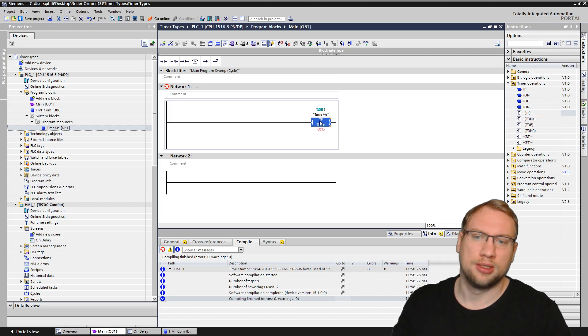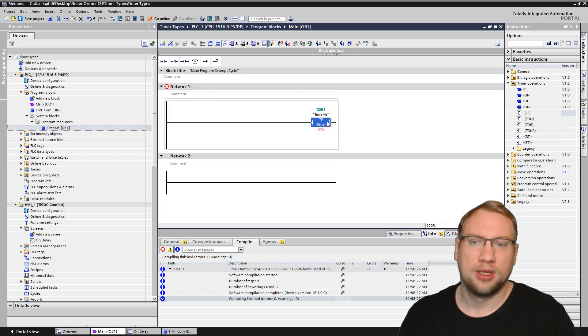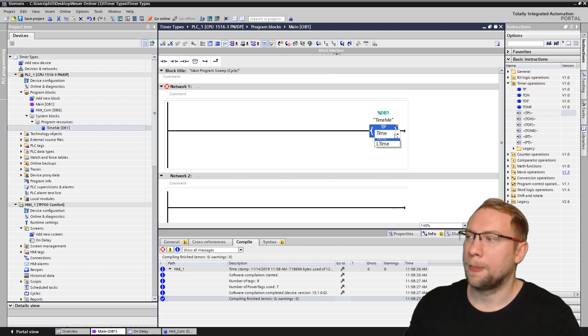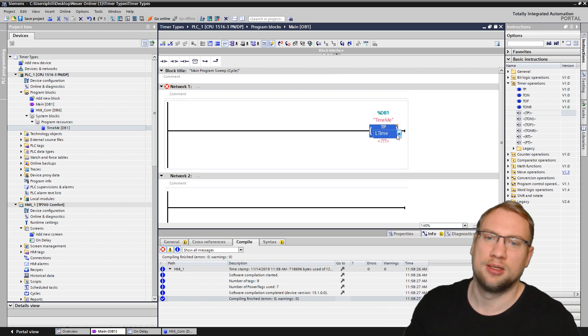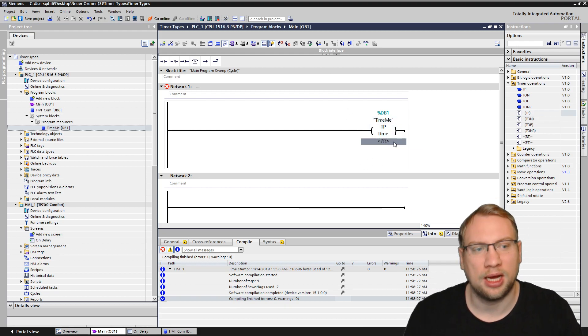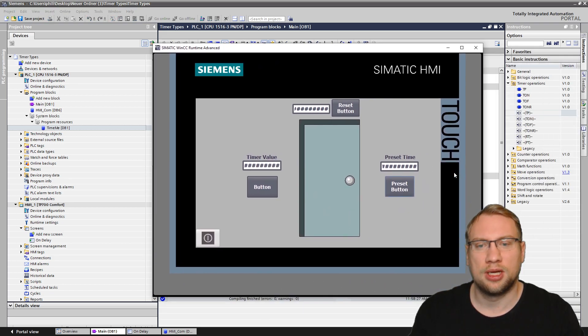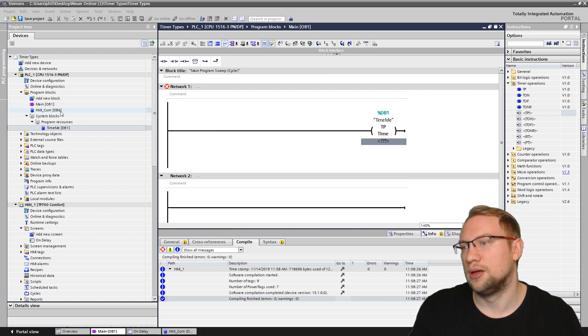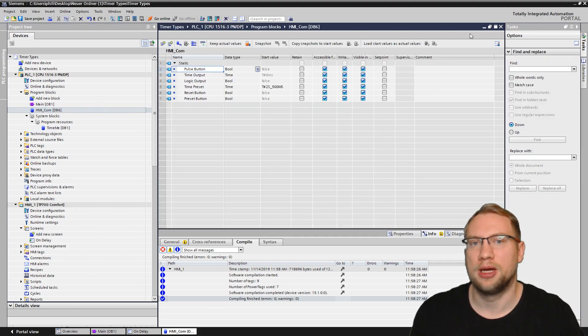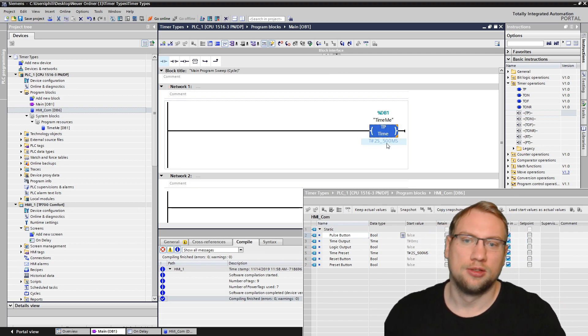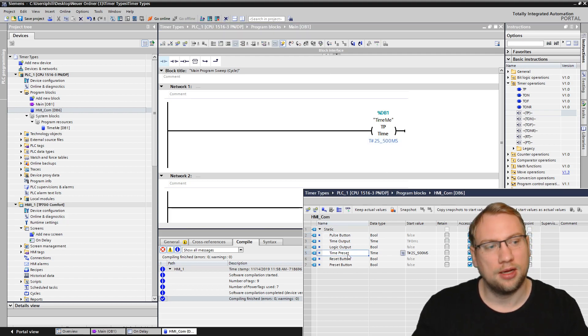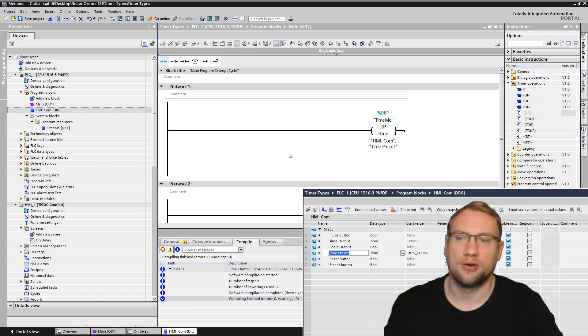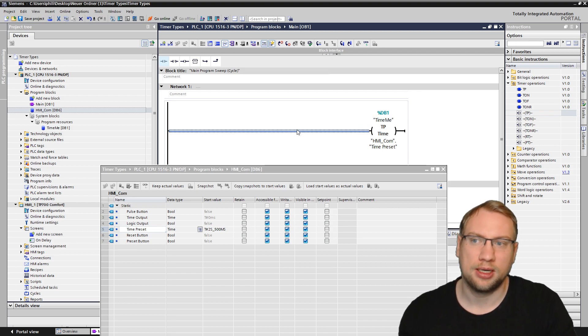And now this instruction here tells the data block, please be a pulse timer. If I want, I can also select any of the other timer types with this. See, it's pretty easy, pretty simple to use. I can also down here choose between time and long time. If I choose long time, of course, my data block won't be fitting anymore because of another data type. On the lower side, I will need just the time, how long I want it to run. And I want this time to be able to put it into the program using the HMI. I want the time should go down here and I have it in my HMI data block that I've prepared. Just drag and drop it up here because I have linked that to the HMI already.